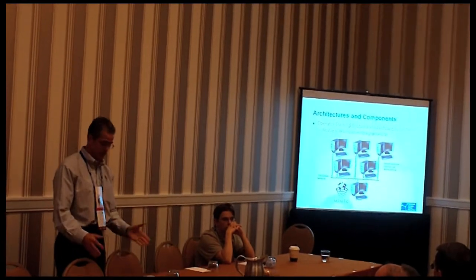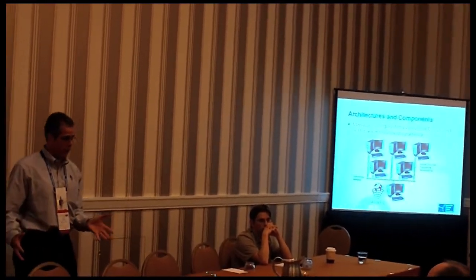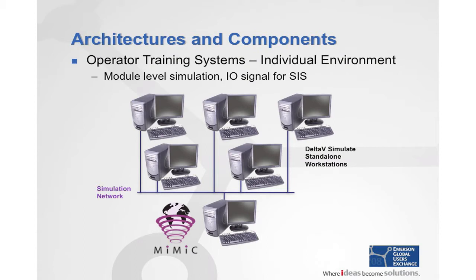This works out very well if you want to set up a training system for four to six operators, cycling through them and giving individual evaluations and testing. More and more, I see this being used in operator training systems. The biggest limitation is that with Simulate Pro, you can only put four to six controllers worth of modules in the workstation. However, four to six controllers worth of modules is really almost a complete span of control that one operator can work with — talking one thousand to two thousand loops, which in most cases is pretty much where you're at.